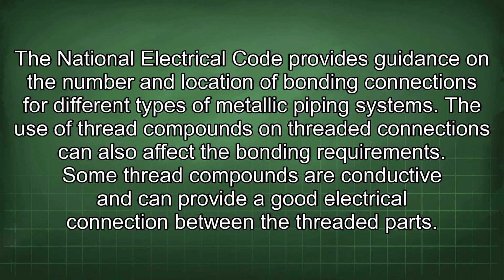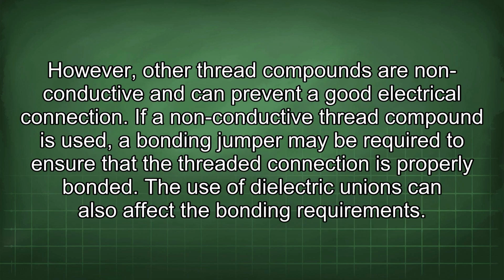The use of thread compounds on threaded connections can also affect the bonding requirements. Some thread compounds are conductive and can provide a good electrical connection between the threaded parts. However, other thread compounds are non-conductive and can prevent a good electrical connection. If a non-conductive thread compound is used, a bonding jumper may be required to ensure that the threaded connection is properly bonded.